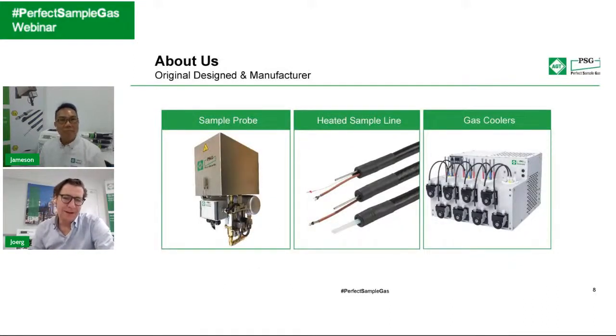Okay, Jameson, I mean, good thing for us is even if it's a hot wet system, you still need a sampling probe and you need a heated sample line. And surely I can tell you the quality of these components really matters. When you have a hot wet system, you just have to ensure that, especially when you measure in environments like waste incineration, where you might have higher acid dew points, every condensate will finally result in the dying of your components because there's so much corrosion then. I think this is the field which unites both types of systems, but at the end, the gas cooler, the gas conditioning system, is something which depends on the analyzer technology which is used.